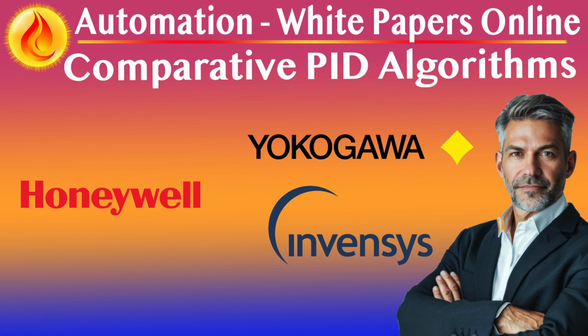Invensys, via its Foxboro Control Objects, FCO, and earlier FB107 blocks, implements ARW and reset logic with more manual setup, especially in older systems. In series forms, adjusting D affects the effective INP, making reset response more dynamic, but harder to tune unless algorithm-specific relationships are understood. In newer Foxborough systems, EcoStruxure Foxboro DCS, the function block language, FBD, supports improved reset management and integration with model predictive and override blocks.